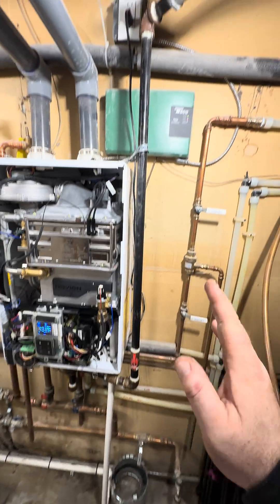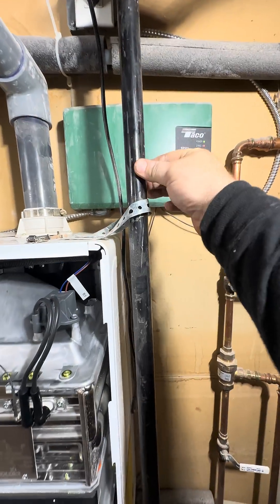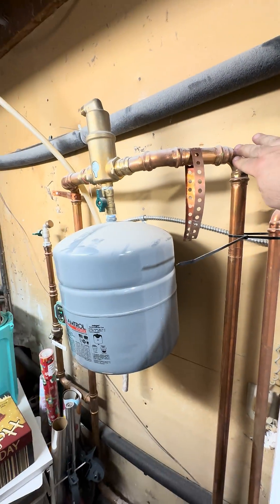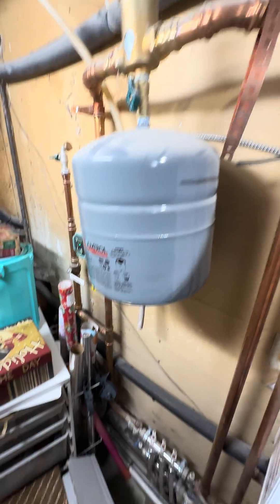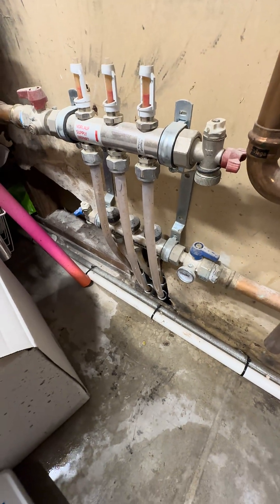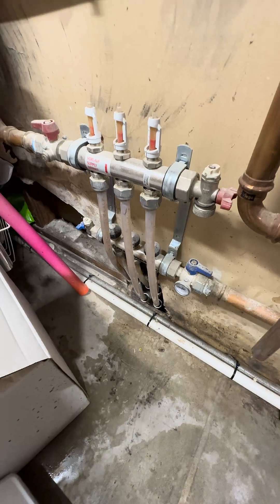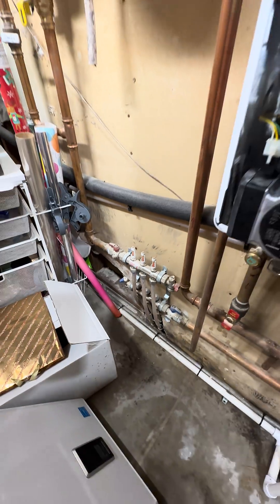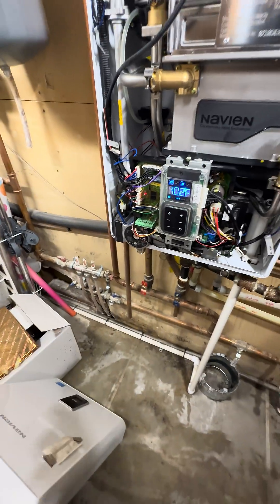Look at this lovely install — look at that wonky gas pipe, that's sweet. I love the zip tie hanger on this piping, down to the three-loop manifold. The bracket is backwards — I've never actually seen anybody do that. It actually took some work to do.